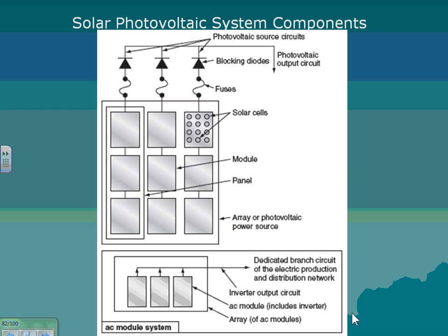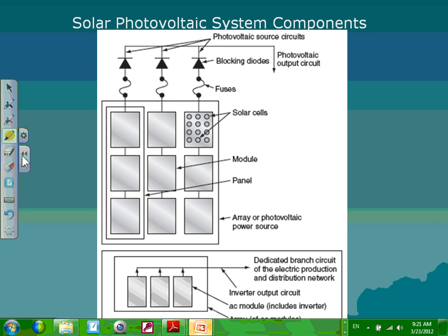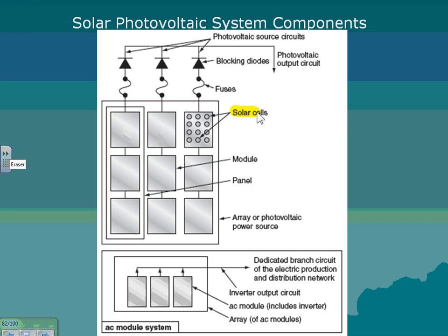Solar system, there are two systems you can install, the AC inverters, AC system or DC system. This is directly from the NEC code book. You guys are familiar with this. What they do is they take all these cells. We all know how it works, right? These photons, light hit these cells, which is semiconductors, and it creates tiny little voltages, tiny little current. We collect these cells, and we end up with each panel giving us 24 volt and 1 amp. Put them in series, you get yourself 600 volt and 1 amp, and then put them in parallel, you get 10 amps if you parallel them.